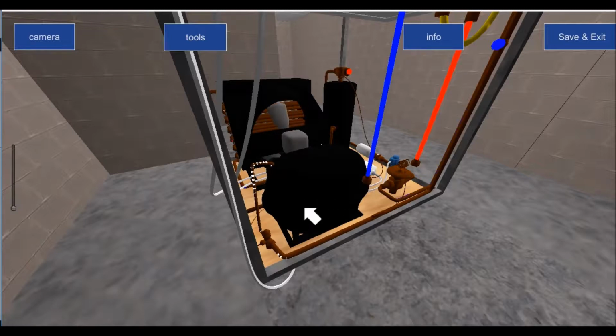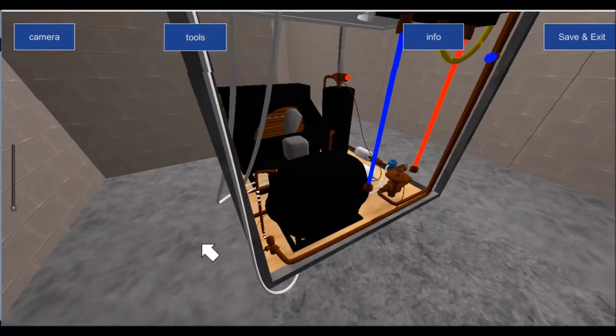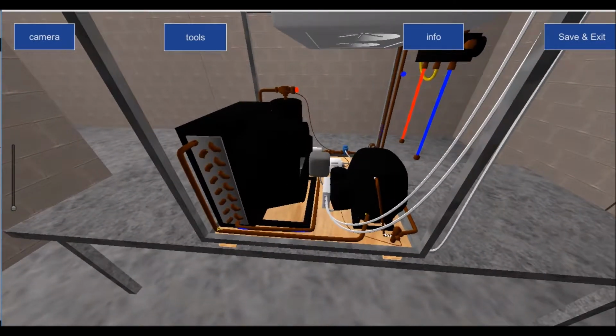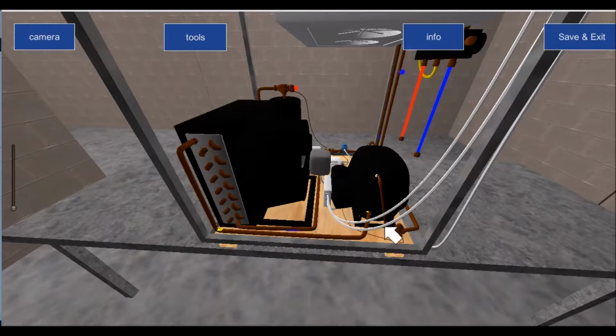So, regardless of what type of compressor, getting back to what a vapor compression system is, their function, regardless of the design or the type of compressor, is to pump refrigerant around the system. So it takes refrigerant from low pressure, low temperature coming back from the evaporator. It sucks the refrigerant that's in the evaporator into the compressor, and then it pushes it from the compressor. So basically by the process of compression, it will convert the low pressure, low temperature vapor to high pressure, high temperature vapor and discharge it into the condensing unit. The purpose of the condensing unit is to desuperheat that vapor. Then it condenses the vapor, and then it subcools it before it exits the condenser and heads along the liquid line through the liquid receiver.